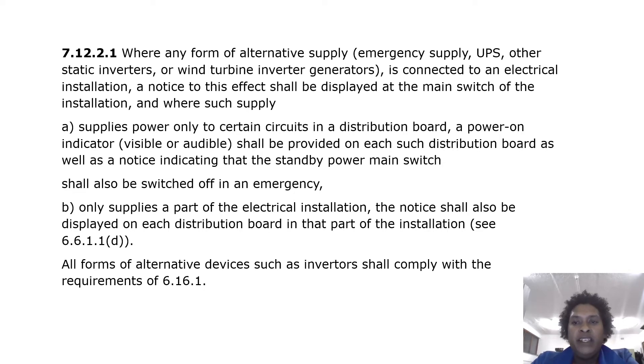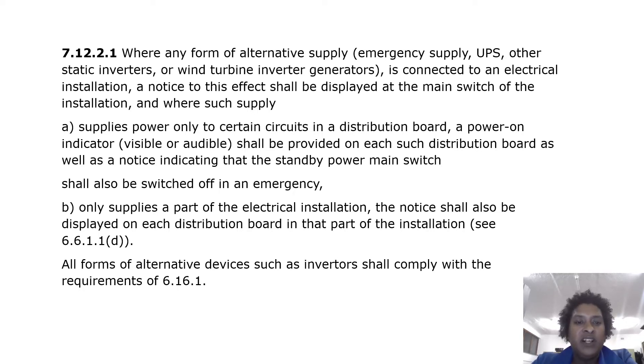Where any form of alternative supply — emergency supply, UPS, other static inverters, or wind turbine inverter generators — is connected to an electrical installation, a notice to this effect shall be displayed at the main switch of the installation. Where such supply provides power only to certain circuits in a distribution board, a power-on indicator (visible or audible) shall be provided on each such distribution board, along with a notice indicating that the standby power main switch shall also be switched off in an emergency.